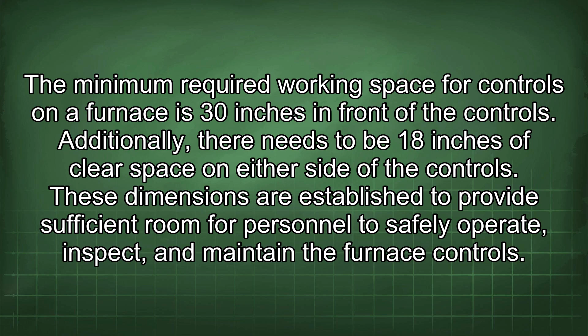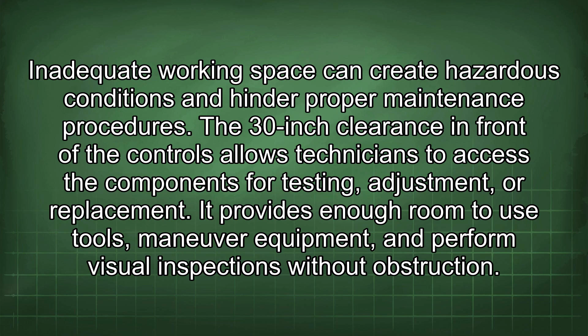Inadequate working space can create hazardous conditions and hinder proper maintenance procedures. The 30-inch clearance in front of the controls allows technicians to access the components for testing, adjustment, or replacement.